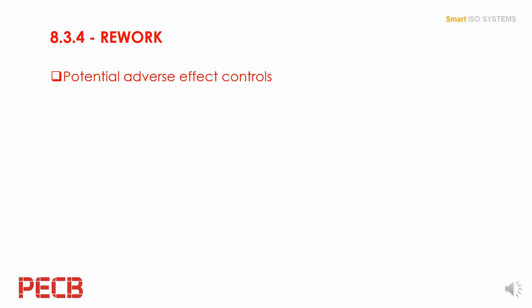Again, this clause is not new. Rework was already included in the current standard as part of controlling non-conforming products. However, in this new section that's been added, it states that if you establish rework, you need to look at any potential adverse effects on the product. Not only that, but it also has to become part of your risk management process. When you decide that a product needs to be reworked, you are required to also consider the implications, and whether retesting has to be done on the product. How does the rework affect the design of the product or any other manufacturing?